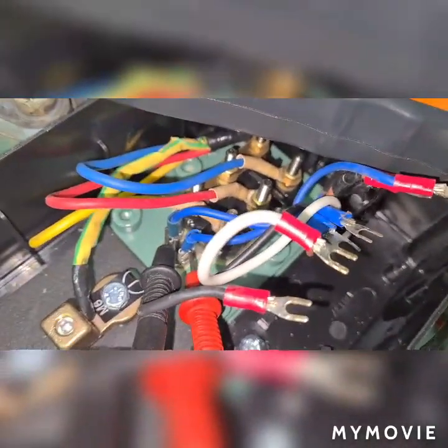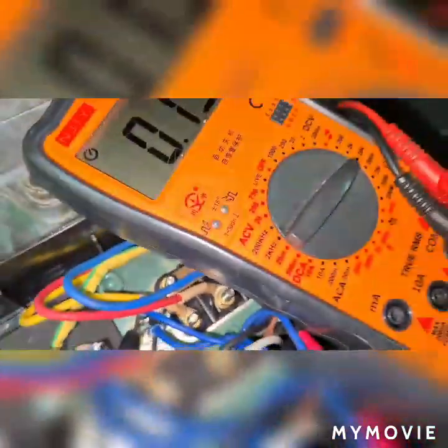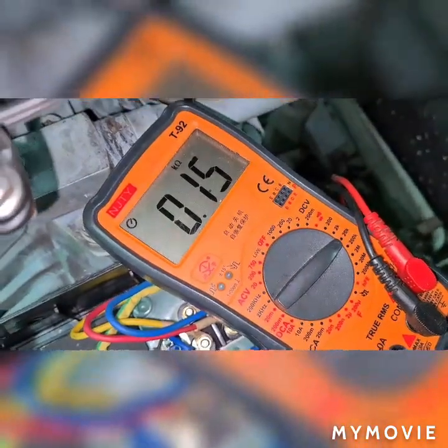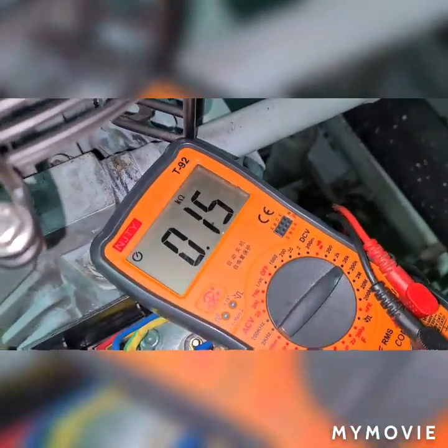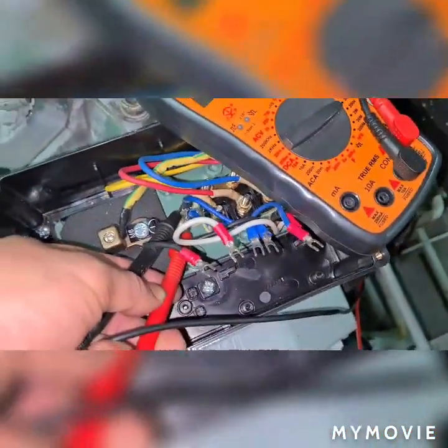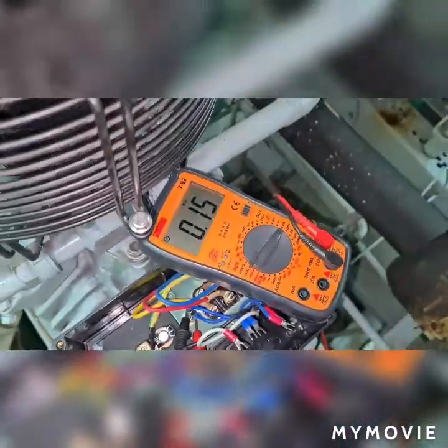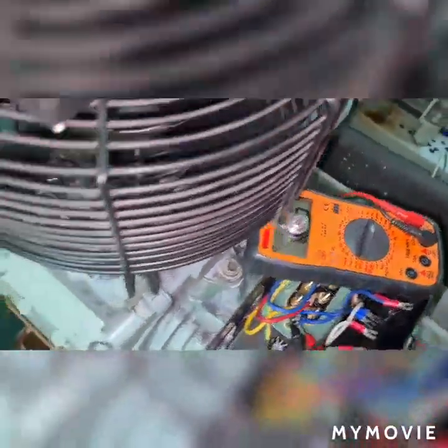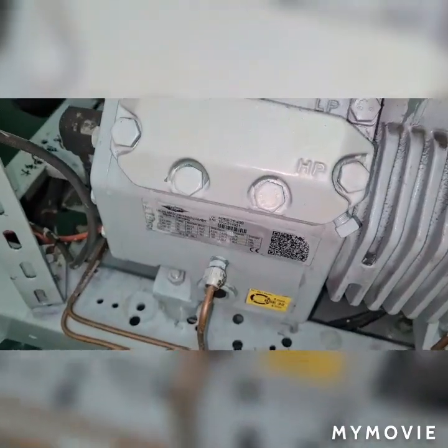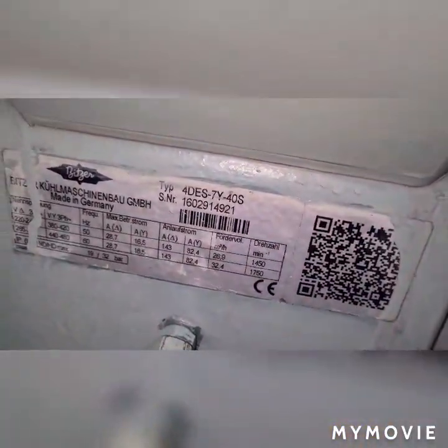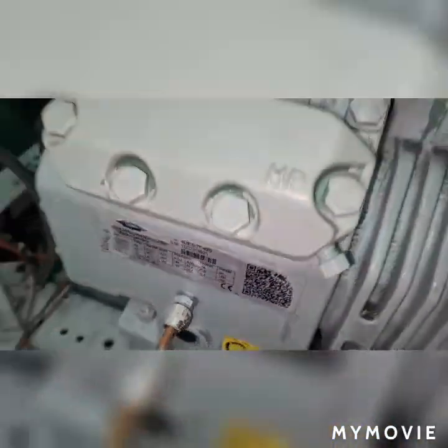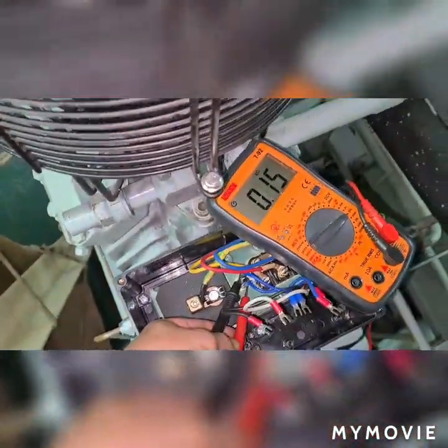As a preview, this motor protector relay works when sensing a resistance of 4.5 kilo ohms. When the resistance says having a 4.5 kilo ohm, this motor protector relay will be able to switch off the motor and stop the motor from running.